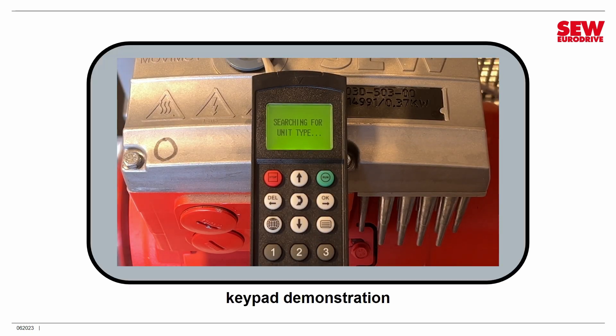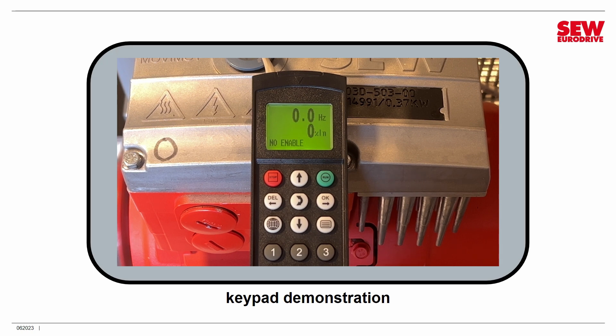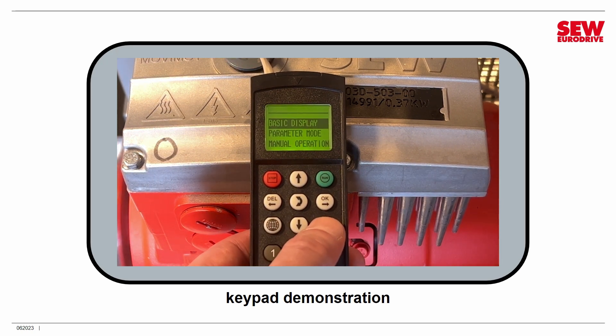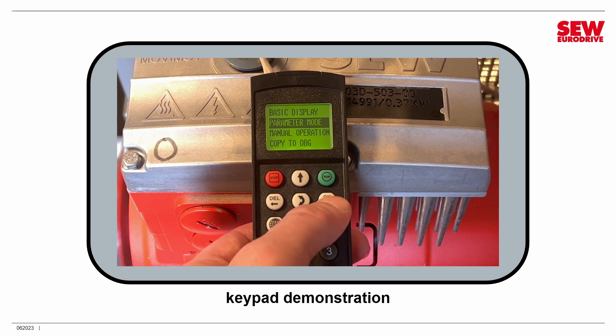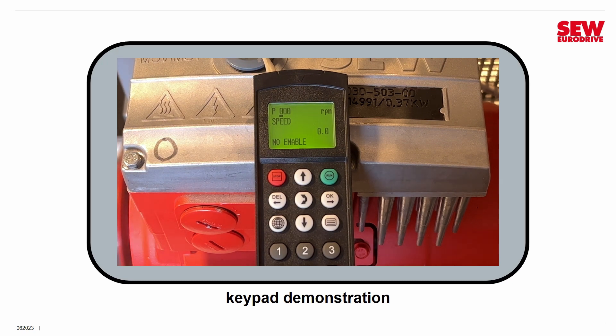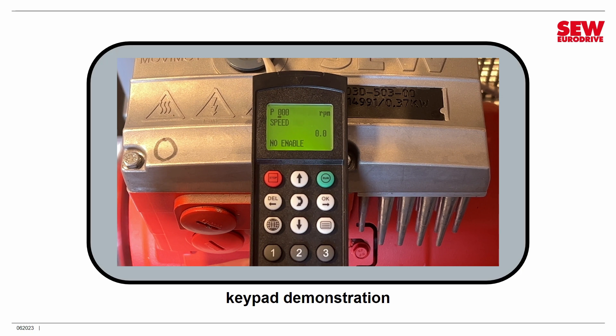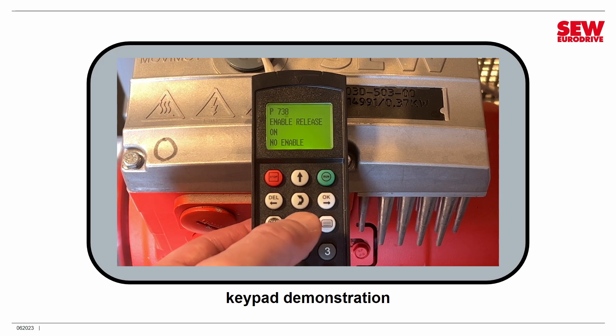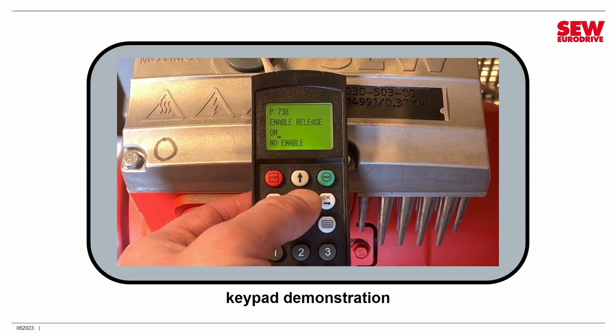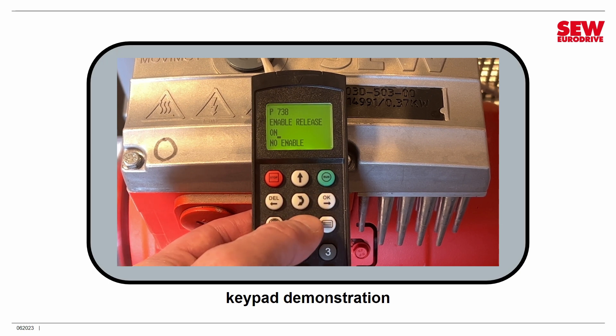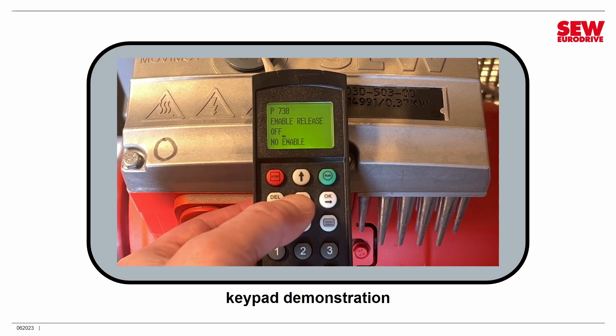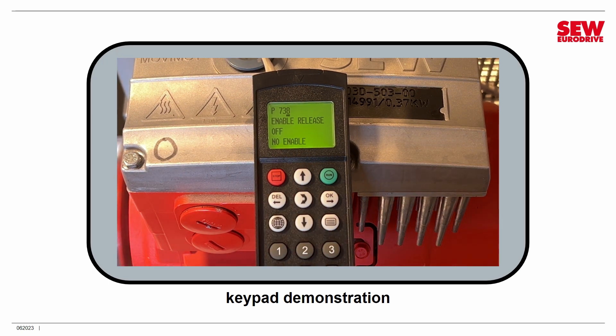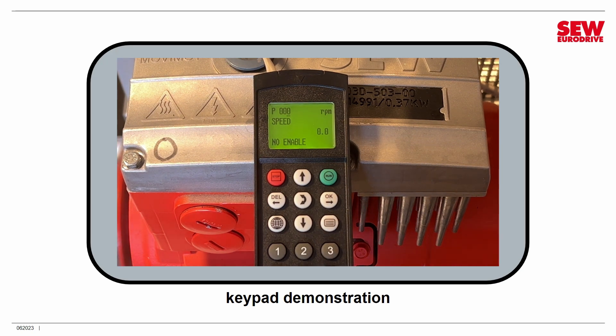All right, well we've plugged our keypad in and turned on the Movimot. You can see it's in expert mode. It identifies that on the keypad. And now we're on the basic display screen. First thing we'll need to do is hit our menu button, and then we pick parameter mode with the arrow keys and then press the OK button. We access parameters by typing in their numbers, so we're going to type in the parameter number that we wish to change. Let's turn that brake enable function off because that's what we want it to normally do. So we'll go to parameter 738, and we have to press the switch button. That's the one in the middle of the keypad in order to change the value of the parameter. Notice when you press it, it goes down there where it says on, and then if you press the up or down button you can change that. We'll change it to off and press OK, and then switch to go back up to the parameter number.